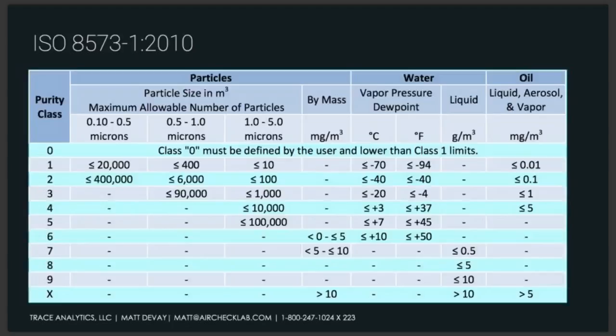So you can say 2 for particles, 4 for water, 2 for oil, which is a fairly common specification that I see for direct contact air for food. You can do things like 442, which is a fairly common one that I see for indirect contact. You also don't necessarily have any obligation to follow the chart exactly. So if you do a risk analysis and it says, okay, well, we might want a class 3 for particles and class 4 for water, but oil, really what we need is 2.5 milligrams per cubic meter. You can make that specification for yourself and have it tested.